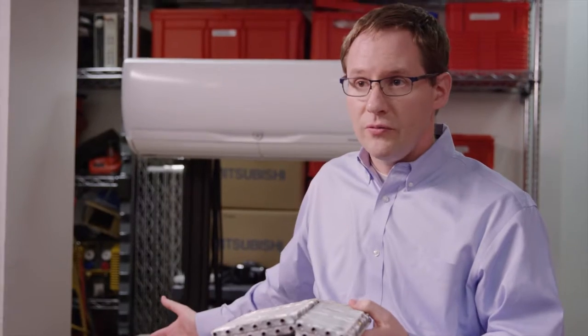Another aspect that we're working on at a system level, so this is on the component level, on the system level, we're also looking at adjusting the amount of refrigerant in the system. What happens today is that when you put refrigerant in your air conditioner, we sell these systems all over the world. You might sell them in Dubai, you might sell them in Atlanta, you might sell them in Minnesota. For every single one of these types of systems, it'll have the same amount of refrigerant in it. But the efficiency of this system is a strong function of the mass. So in Minnesota, you might actually want to put a little bit more refrigerant in. In Atlanta, you might want to put a little bit less refrigerant in, and that's not done today.